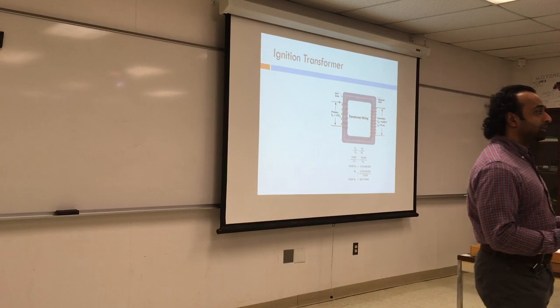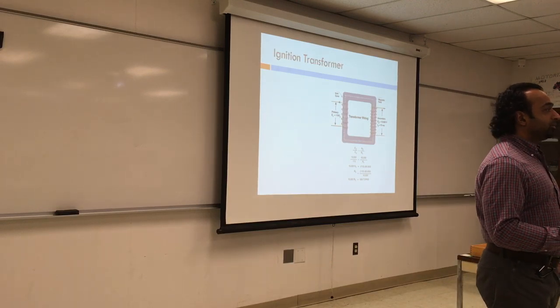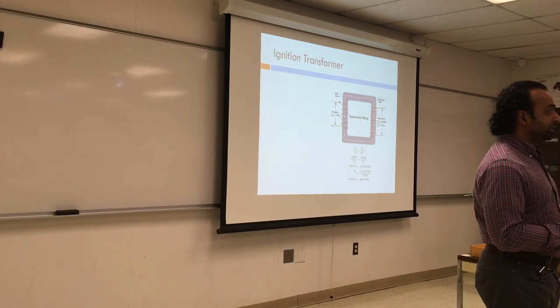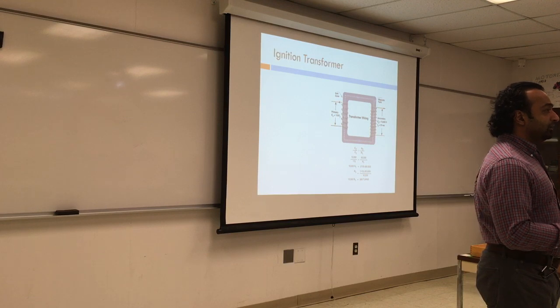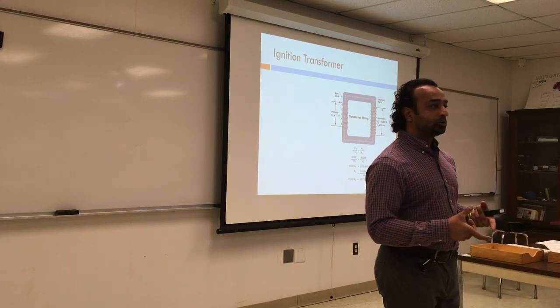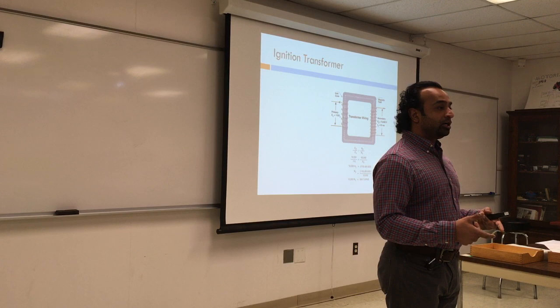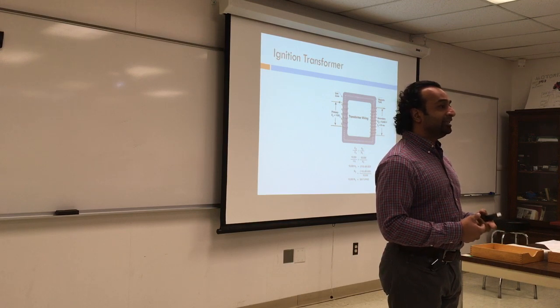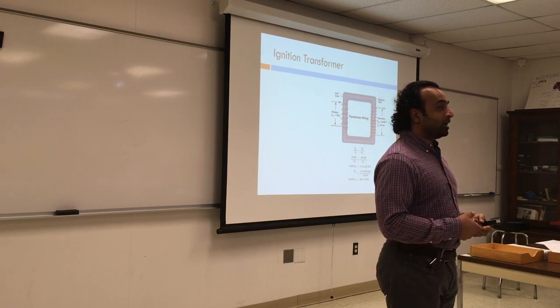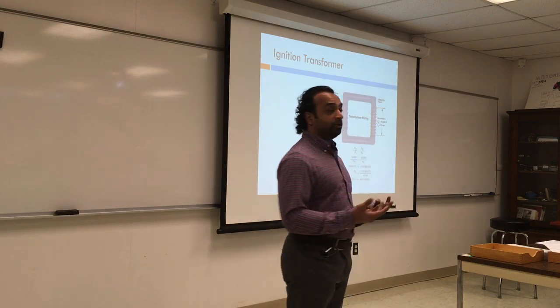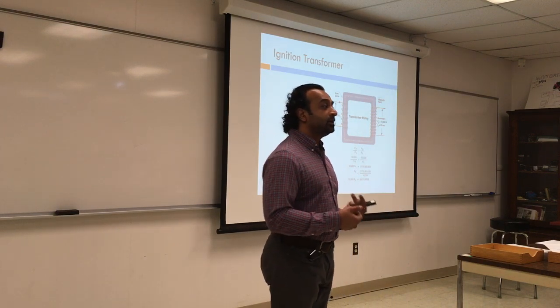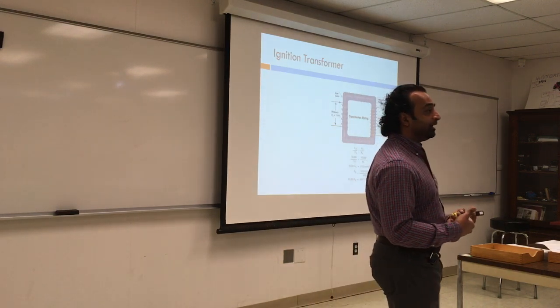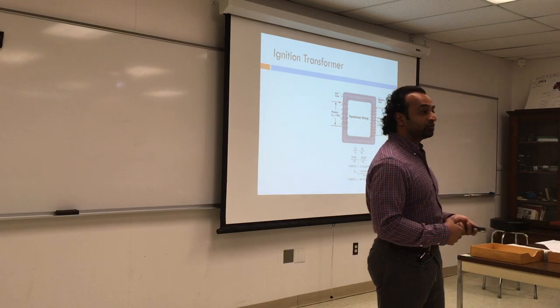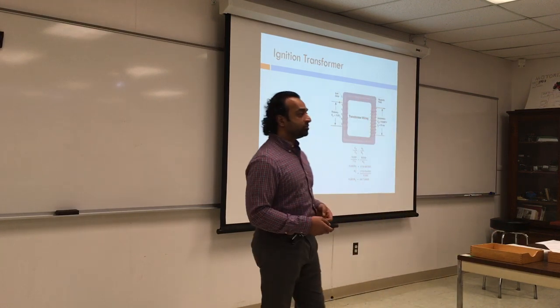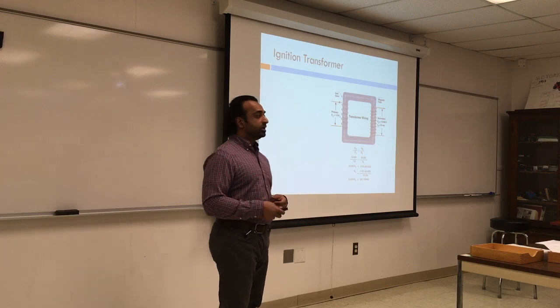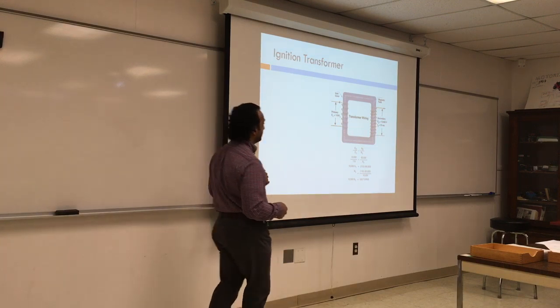So the transformer. We said also at some point, electronic igniters. Try to distinguish between electronic igniters and transformers. Electronic igniters are very lightweight and inexpensive, and they use an electronic board to intensify the current and can produce up to 17,000 volts. They either work or they don't. But based on replacing them so many times, people went back to using transformers. So you will see the heavy transformers in the installations.